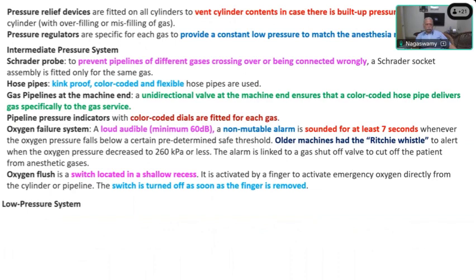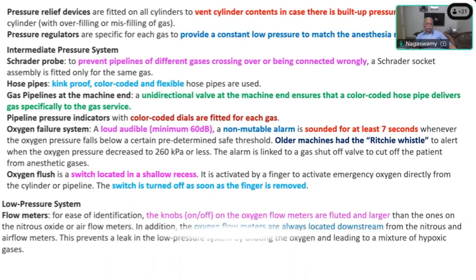So that has been avoided in the modern day workstations. Next comes the low pressure system, which starts from the flow meters, and each one has a knob to identify it. For oxygen, you have a little larger knob with larger flutes. It is color coded, and the name of the gas is also written there.